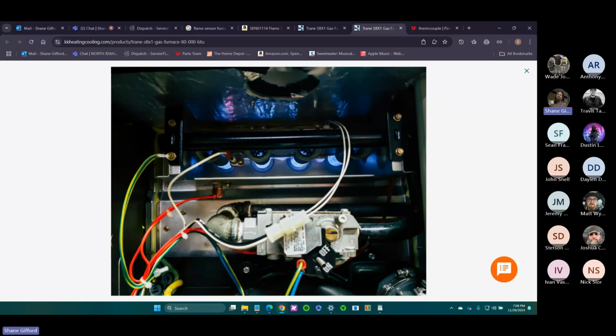And we've seen those in captive air units. You've seen them in tons of different kinds of gas packs. You're good. Once that switch makes, the board goes, okay, we sent voltage through that circuit, we got it back, go ahead. In this instance, it's all timed. So once it runs through all its safety checks, it's going through your rollouts.